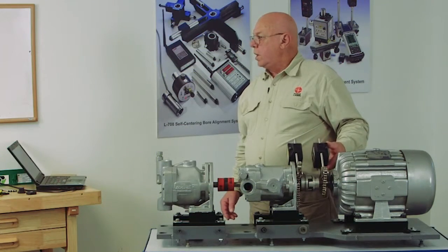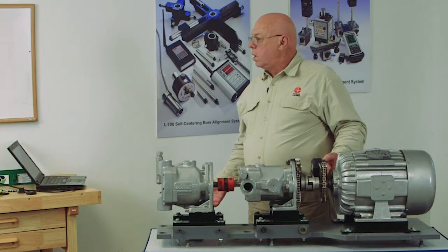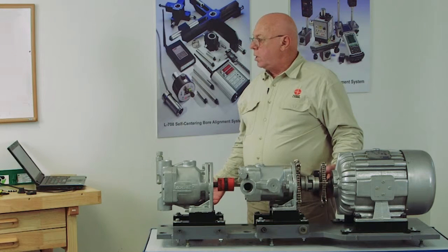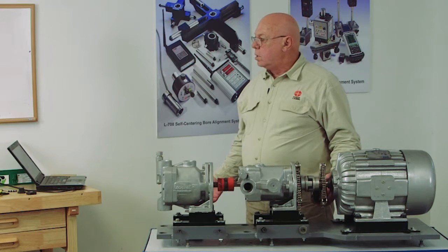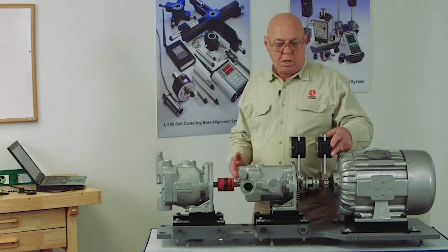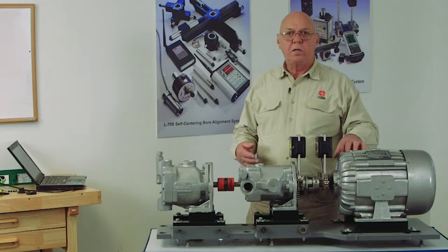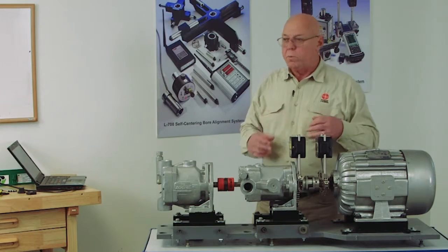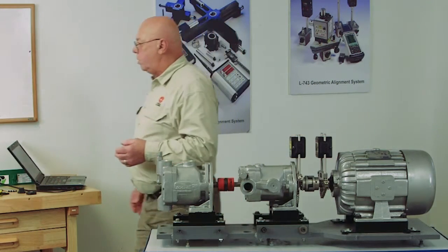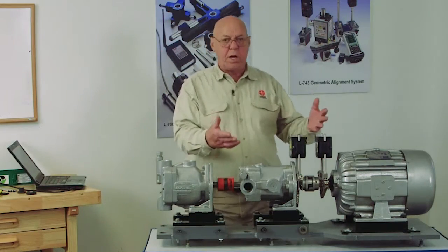Now, a lot of people like to do this in 4 decimal places because they want precision, but from previous experience, I can tell you nothing's going to repeat to 1/10,000th of an inch in something like this. There's clearance in the bearings. These are not tapered Timken bearings, they're roller bearings, so you're going to have some non-repeatability. I'm going to accept that. I have some deviation here, that's common, especially on a pumping motor like this.